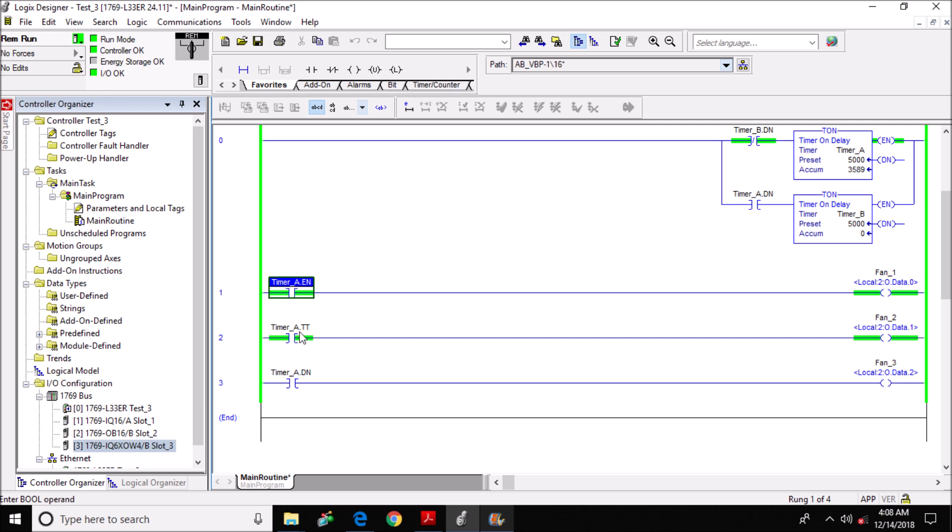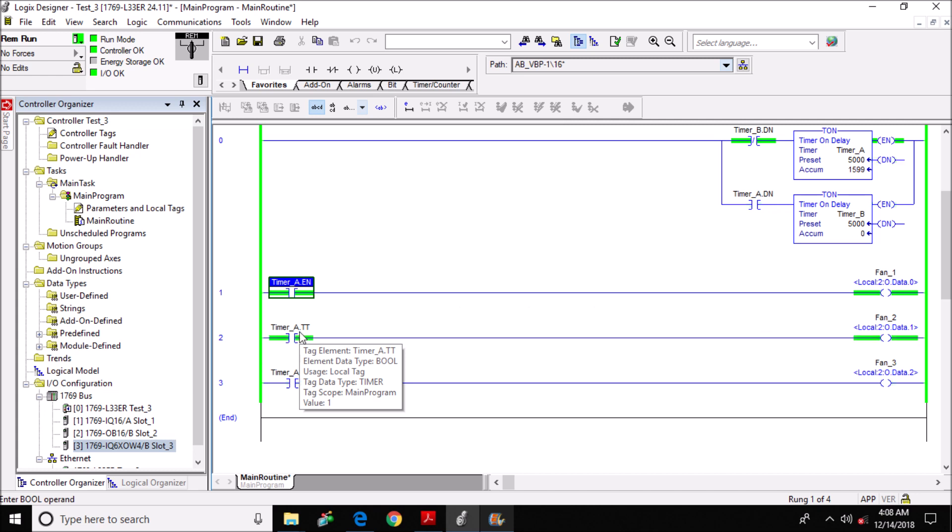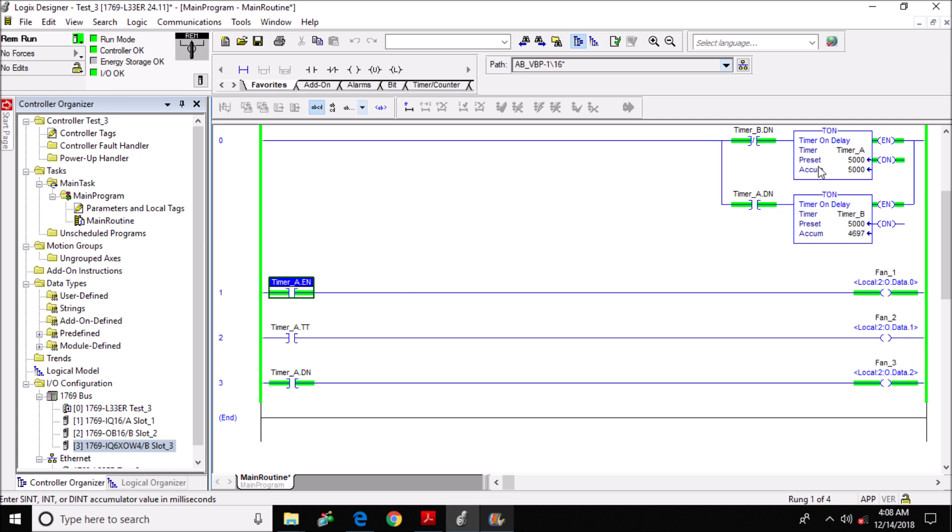Now I'm going to move down to the timer timing bit here. The only time the timer timing bit is true is when the timer is timing, so the accumulated time must be below the actual preset time and the timer must be enabled. Now the timer done bit down here in rung 3 is set anytime the accumulated time is equal to or greater than the preset value of timer_a.